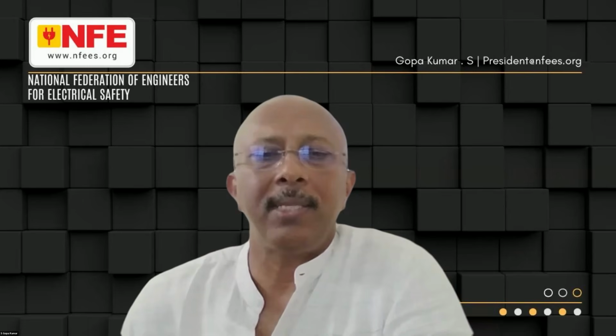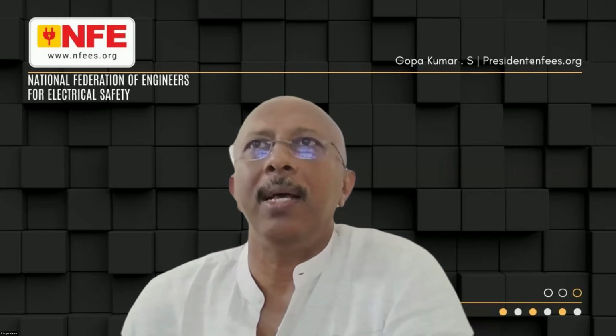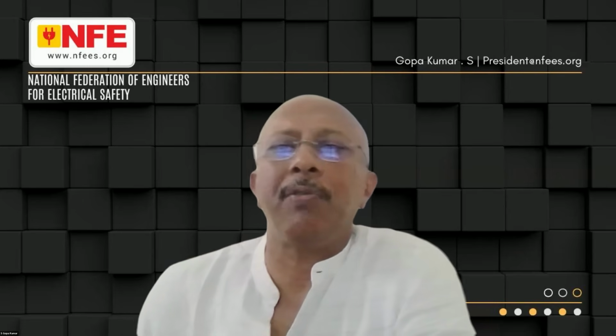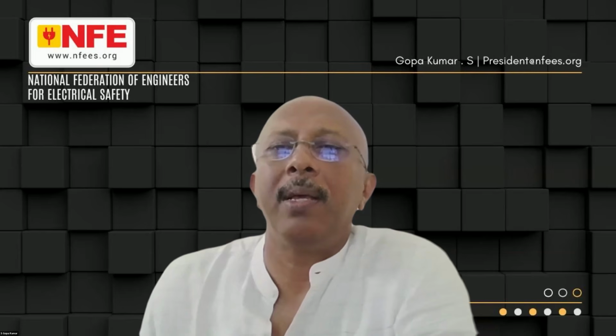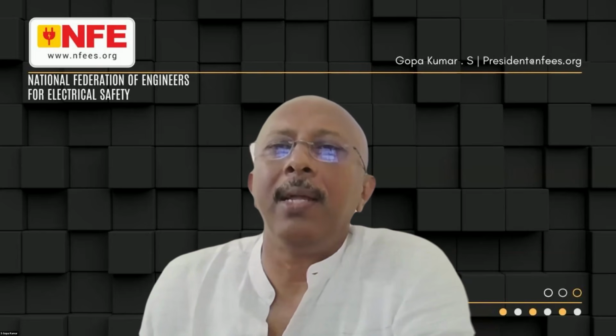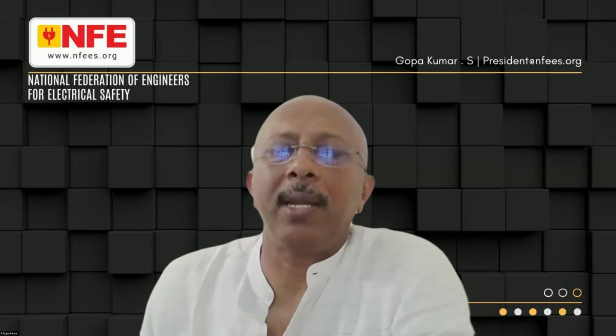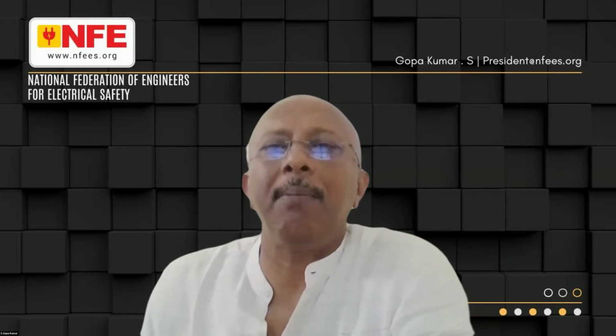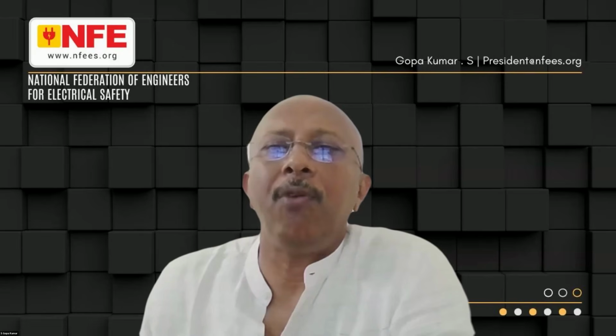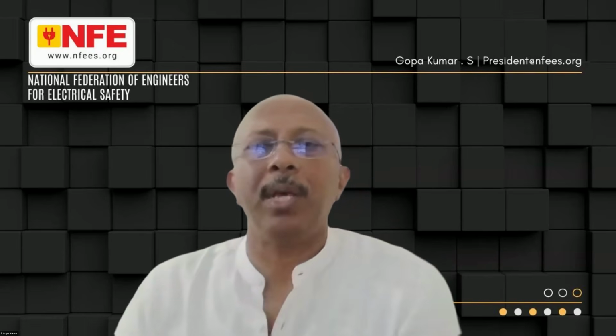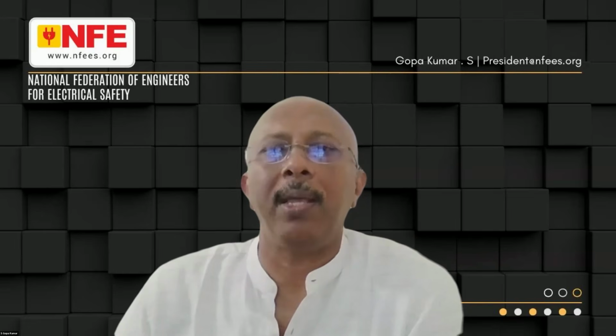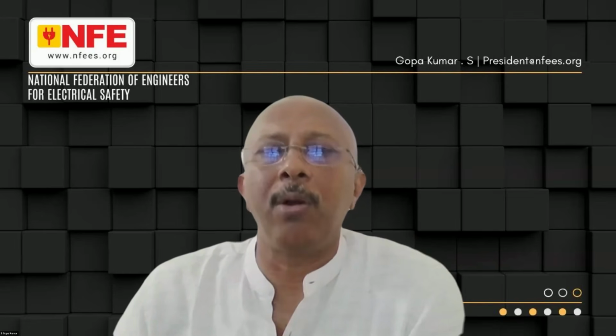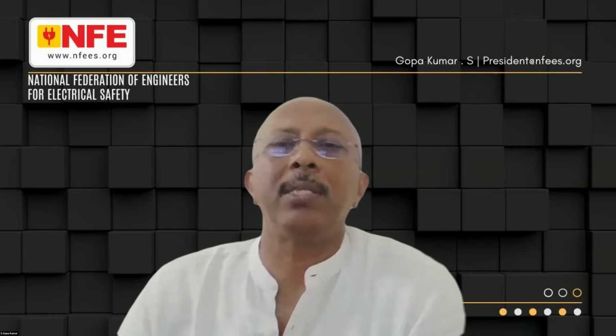So these are already improved in most of the biomedical equipment. As I said, during the installation of the electrical equipment, during selecting the biomedical equipment, you should look into the requirement of all these equipment and you should understand and you should make a system so that your system is functioning properly. That means even if the neutral to earth potential is, let's say, 5 volt, 10 volt, the electronics is able to work.